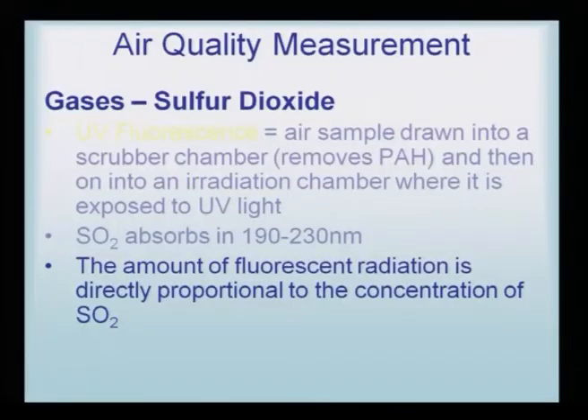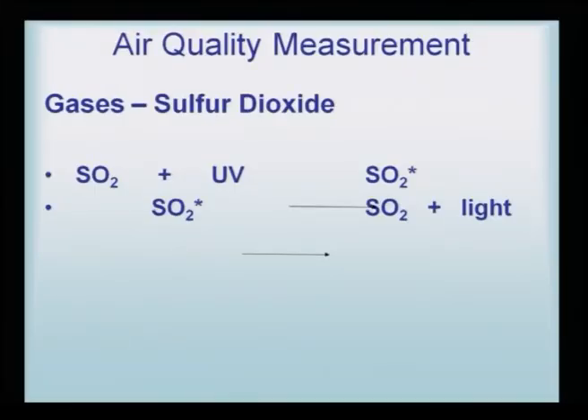The amount of fluorescent radiation is directly proportional to the concentration of the sulphur dioxide, because only that much will be absorbed as there are sulphur dioxide moieties present. As I said earlier about UV radiation and absorption, the concentration is always proportional to the absorption unless there is some other kind of chemical reactivity taking place. So, when sulphur dioxide reacts with UV light, it produces SO2*, and this SO2* then emits light and becomes SO2. This is the procedure that takes place.